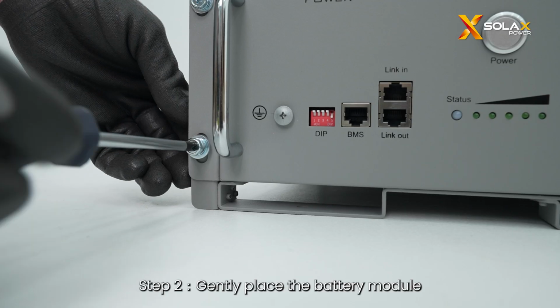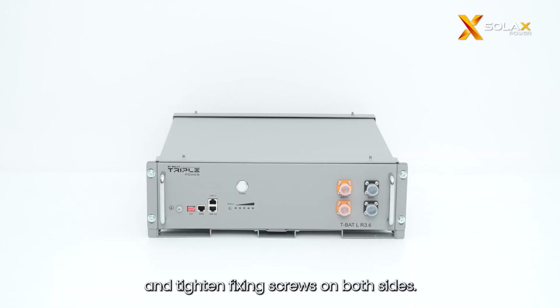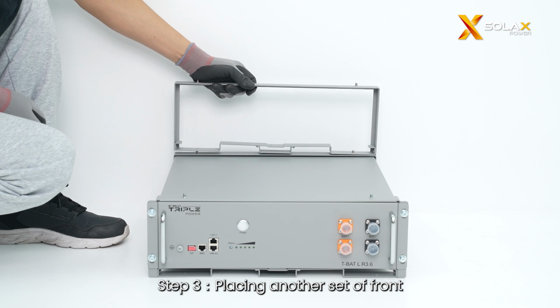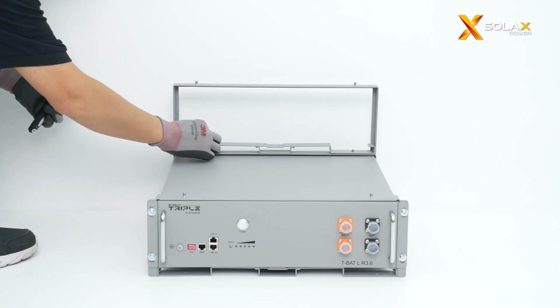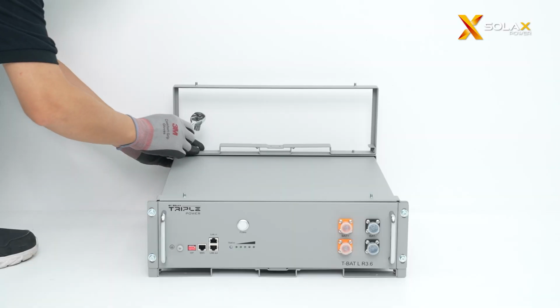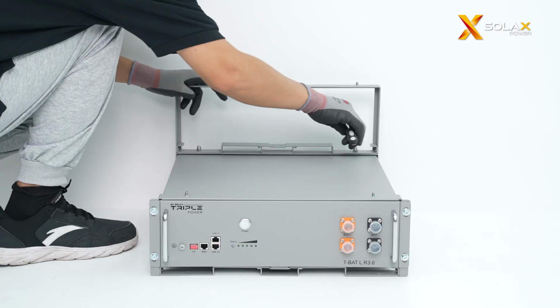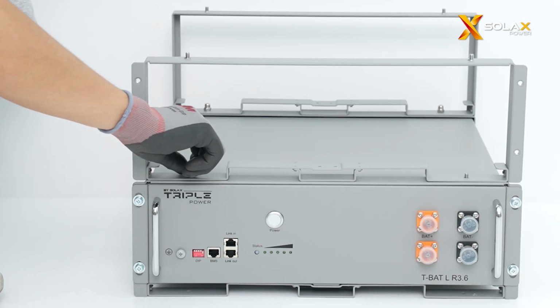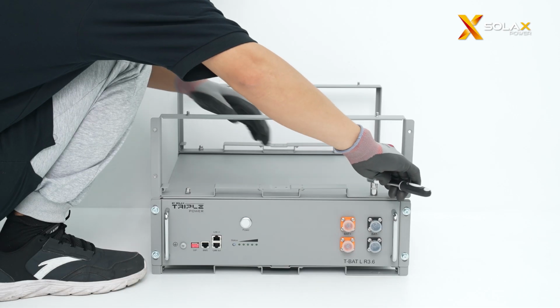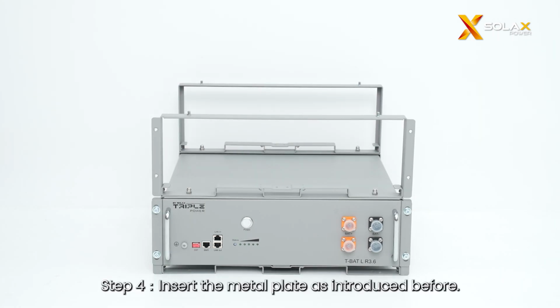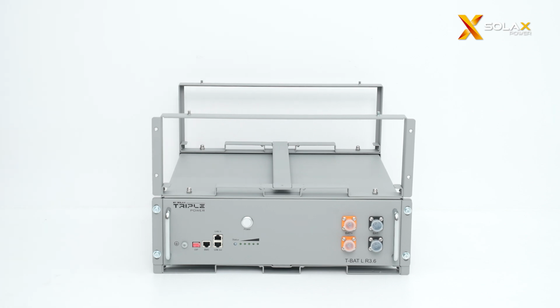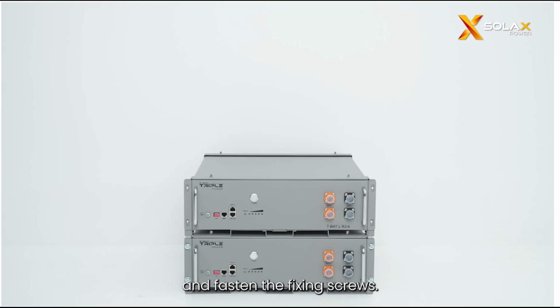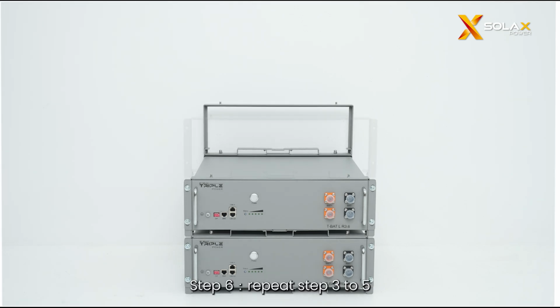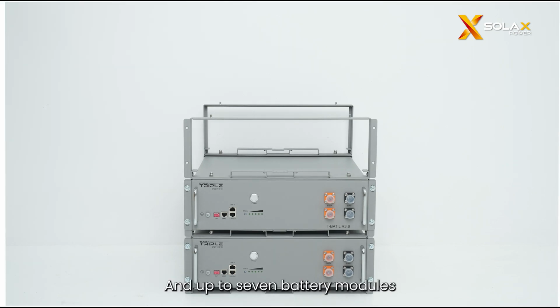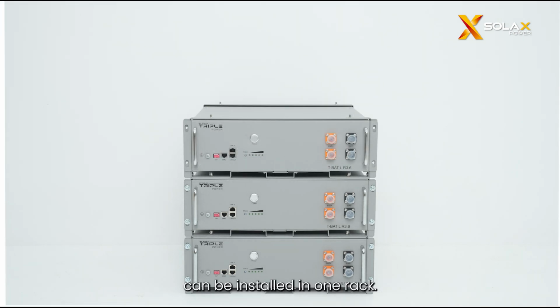Step 2. Gently place the battery module into the assembled rack, and tighten fixing screws on both sides. Step 3. Place another set of front and rear side supports on the first battery. Tighten the cap nuts. Step 4. Insert the metal plate as introduced before. Step 5. Gently place the second battery module and fasten the fixing screws. Step 6. Repeat steps 3 to 5 to mount the remaining battery modules. Up to 7 battery modules can be installed in one rack.